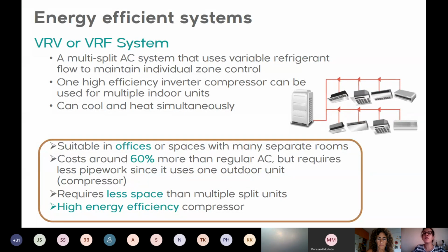Another advantage of this type of system is that it has the capability to provide cooling and heating at the same time, so we can be cooling one room and heating another at the same time. Normally this isn't the case in a house, but take the example of an office with a data center that needs cooling throughout the year, even during winter. A VRV system is able to provide cooling for the data center during the winter and at the same time heating for the rest of the space in a really efficient way.